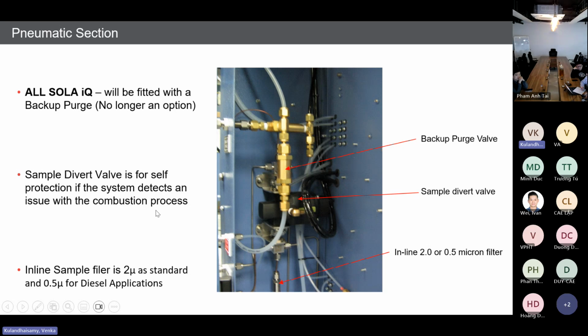the return line. Whenever there is any alarm from the analyzer, that means any common failure alarm or some type of warning alarm, the sample is automatically cut off from going to the injection valve and sent to the return line. So the valve will not inject any sample. So you can safeguard the pyrolyzer from contamination by excess process sample injected to the injection valve. That means the Valco injection valve.